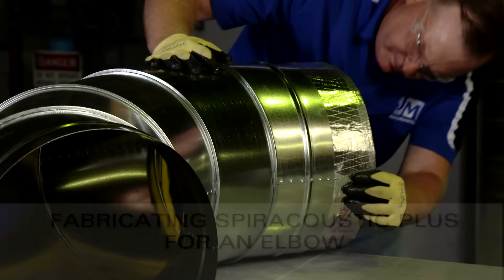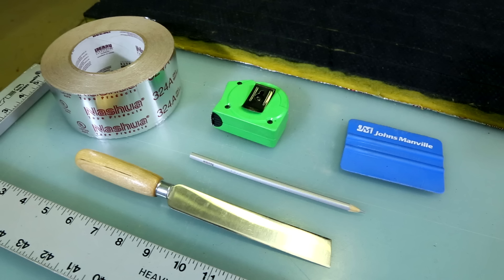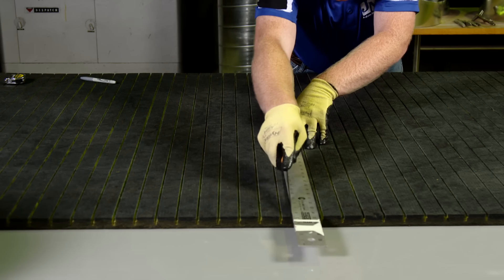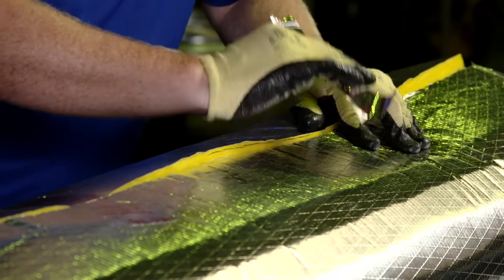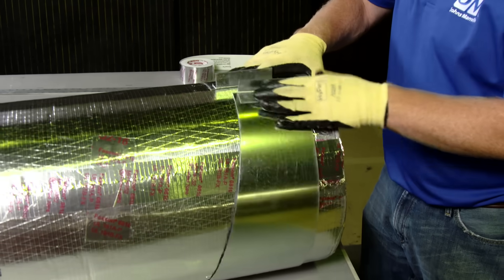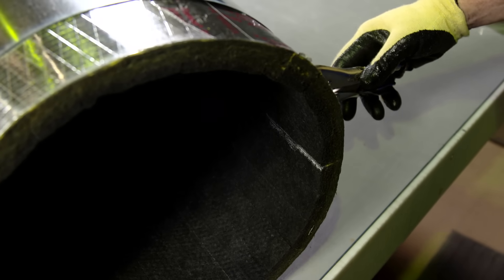Next, let's look at what it takes to fabricate Spiracoustic Plus for an elbow. You will need locking pliers and draw bands shaped as gore patterns, in addition to the standard insulation materials previously mentioned. First, calculate the circumference of the pipe by multiplying pi times the diameter. Then measure and cut the length of the Spiracoustic Plus to 3/4 of an inch less than the circumference. Roll and tape the insulation as you would for a straight section of duct. Once that's complete, clamp the end gore band around the end of the insulation, ensuring that the clamp of the gore band is not aligned with the seam of the Spiracoustic Plus material. Then mark the seam where you clamped the band. You will use this mark to ensure that the Spiracoustic Plus is exactly where it needs to be within the elbow.